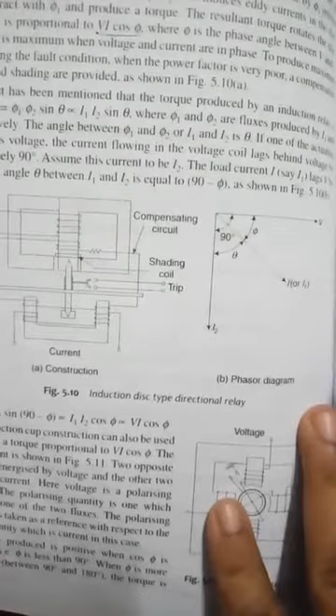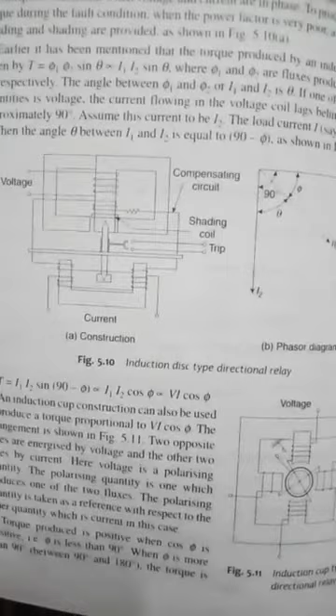Torque is proportional to VI cos phi. Phi is the phase angle between V and I. Torque is maximum when voltage and current are in phase. To produce maximum torque during the fault condition, when power factor is very poor, compensating winding and shading are provided. So torque produced by induction relay is given by T is equal to phi 1 phi 2 sin theta or I1 I2 sin theta.